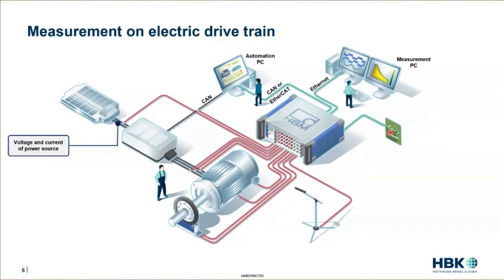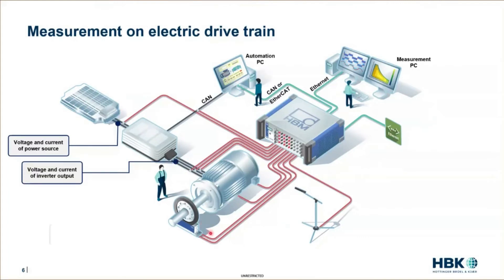In addition to that, we want to typically measure the output signals of the power inverter, which are the input currents of the machine as well. We have in this case a three-phase machine, and in order to calculate the efficiency of such a machine, it is necessary to also measure the mechanical quantities — torque and speed — which define the mechanical power.